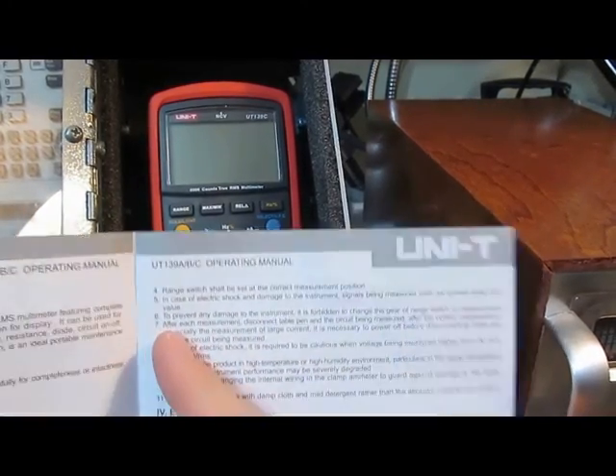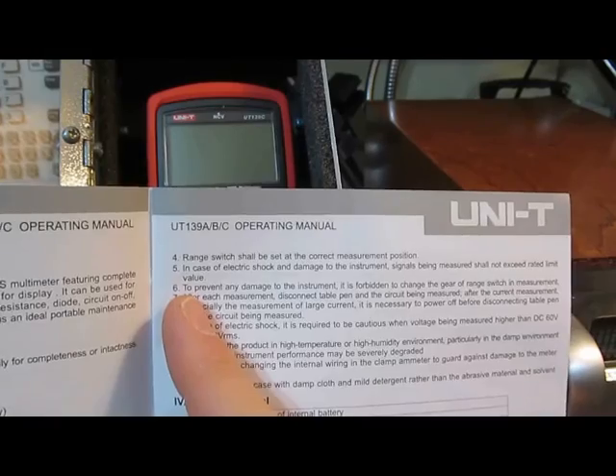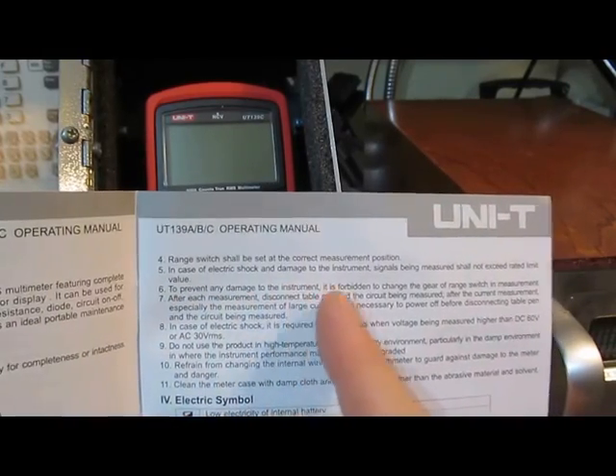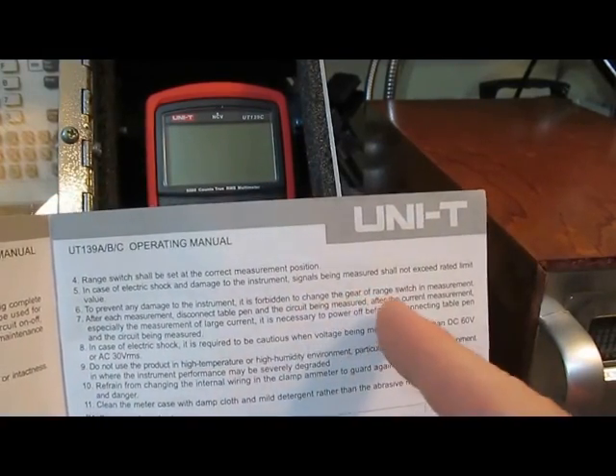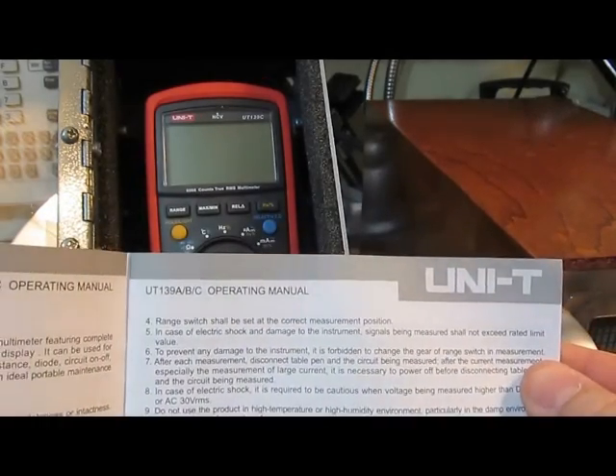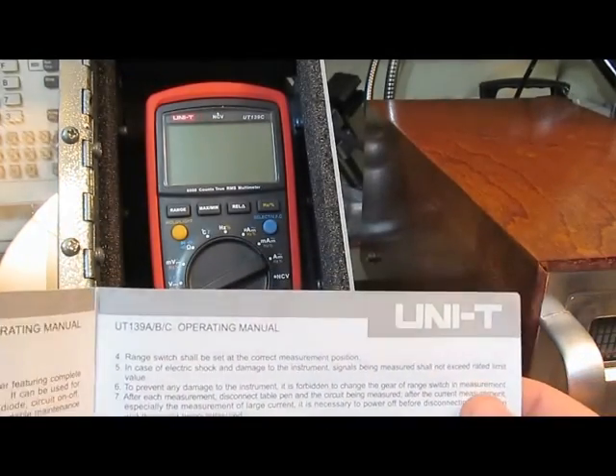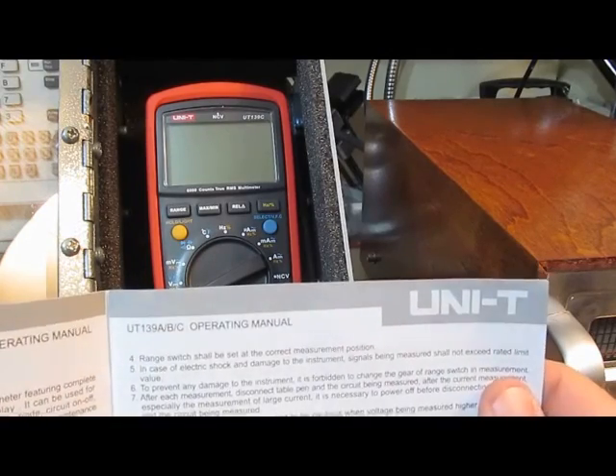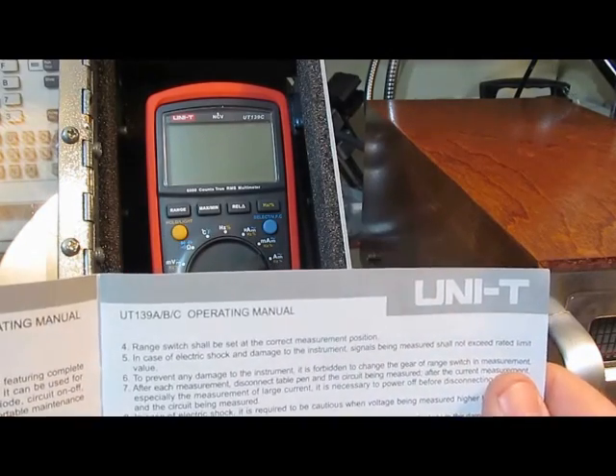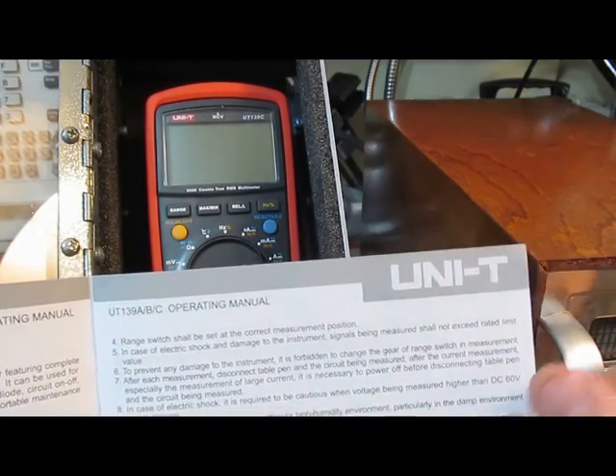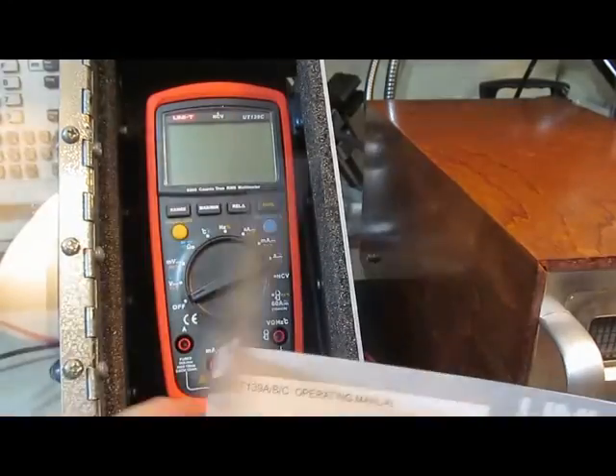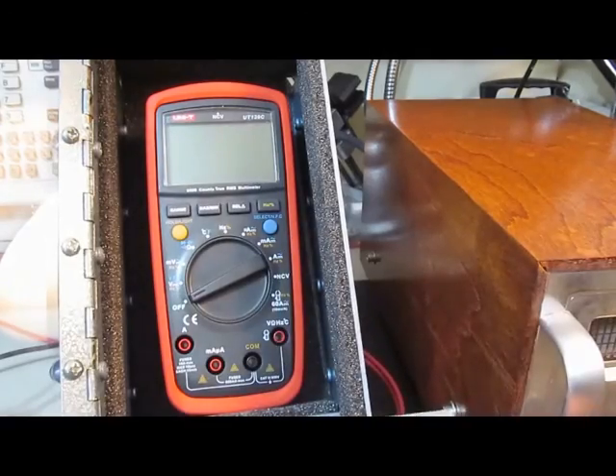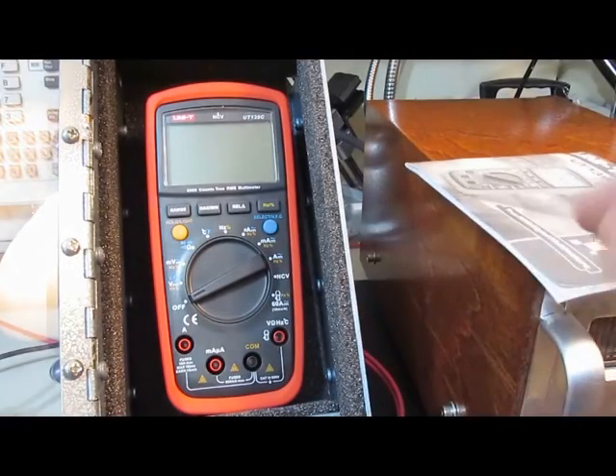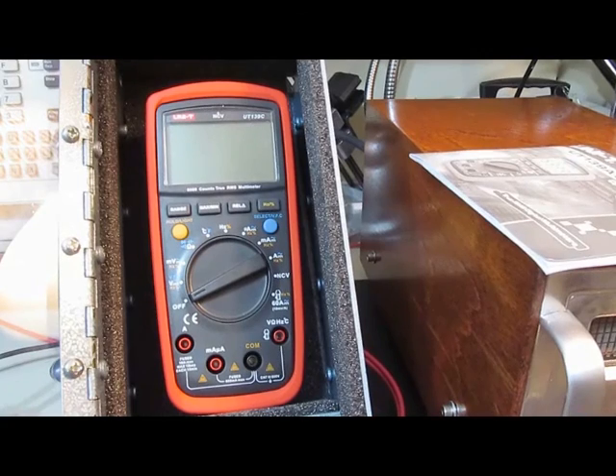So before we run the test here, this is on page 2 of the manual, and you'll see item number 6 here. I don't know if the camera will pick this up, but it says to prevent any damage to the instrument, it is forbidden to change the gear of the range switch in measurement. Now you know what that means. That means if you've got this thing hooked up and you're taking a measurement and you want to do something else, disconnect it, change the switch, reconnect, and take your measurement. So the company is telling you, don't do this test that I'm about to do. Okay? But you know that's not what's going to happen. People are going to rotate that switch while the thing is live.